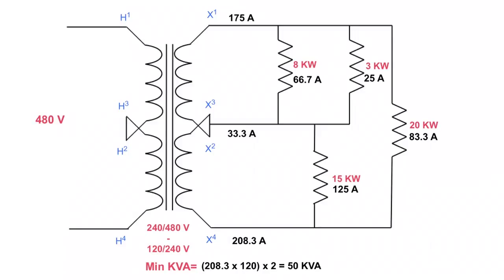You're not generally going to rate your transformer right to the minimum — you'd get a bigger size than 50 KVA in case you want to add more loads in parallel. But our problem today was to determine the minimum KVA. So remember: work out each line current, take the higher of the two line currents, multiply it by the winding voltage to get the KVA, then multiply by two if you have a dual winding transformer. That gives you your minimum KVA.